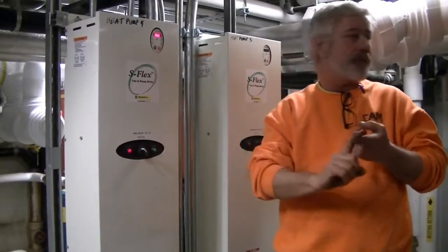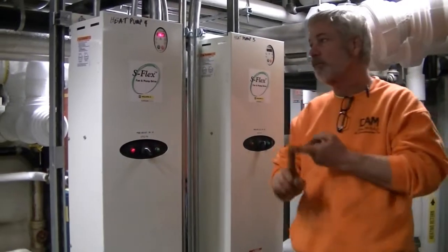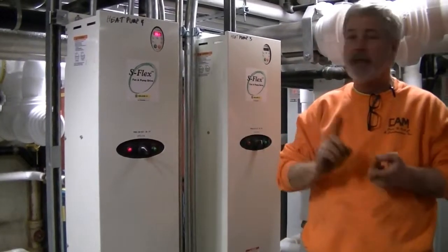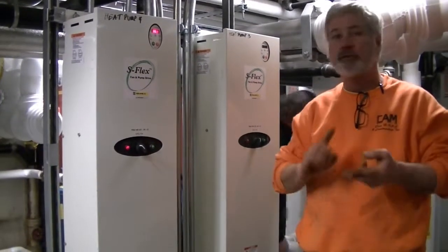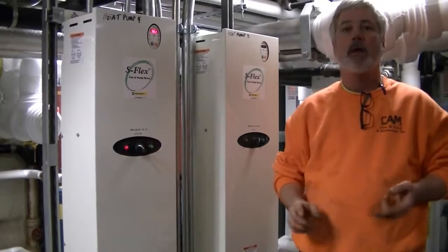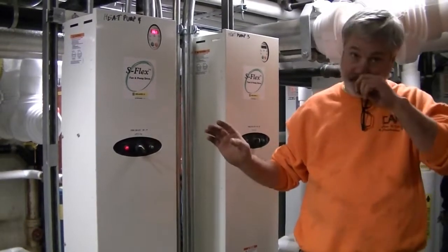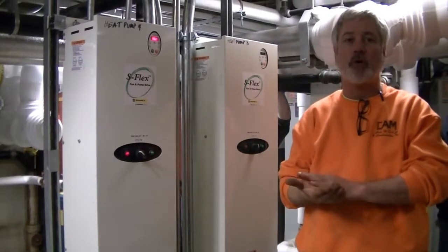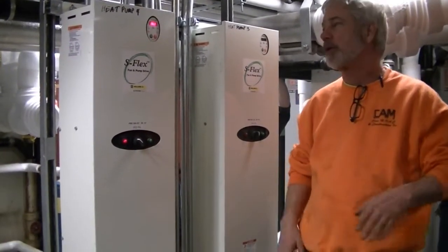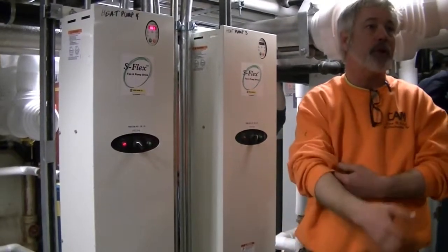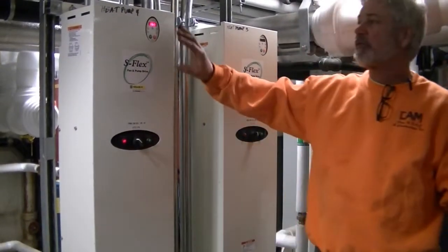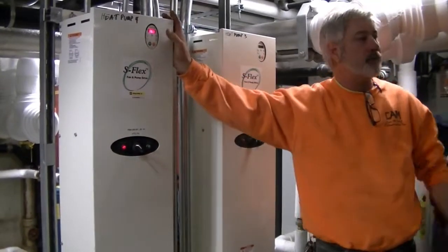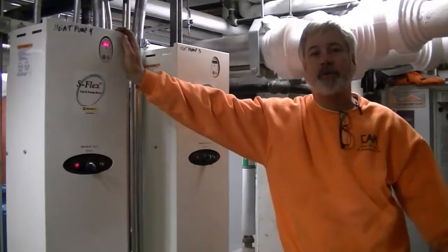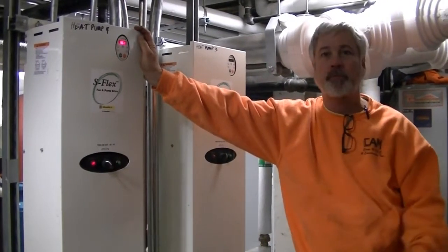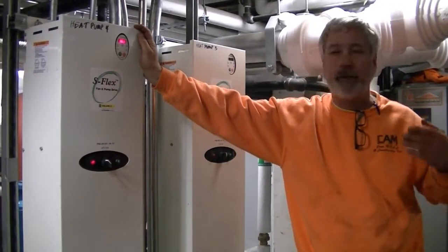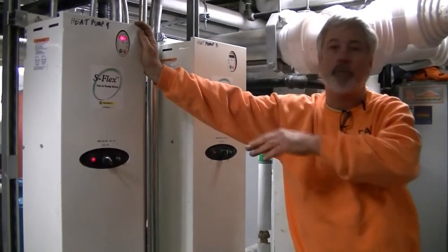Meaning the high frequency, what the maximum allowable frequency output is on the drive, that gets you your design GPMs, and then there's a low limit frequency. Motors on variable frequency drives do not like running down below a certain RPM or a certain amperage. You drop down below that, the drive trips out, and then you've got a nuisance call, you have to come in and reset it. So this has a 15 hertz minimum command. Anytime the drive is called on, we run the pump set, it's usually 15 hertz. That way the motor protection works. Then it'll ramp up and down according to what the set point is on the DP sensor.